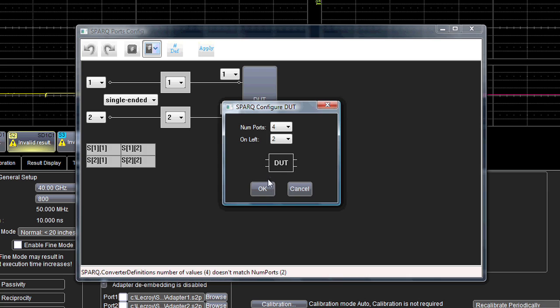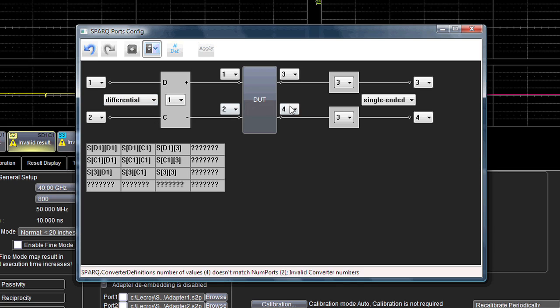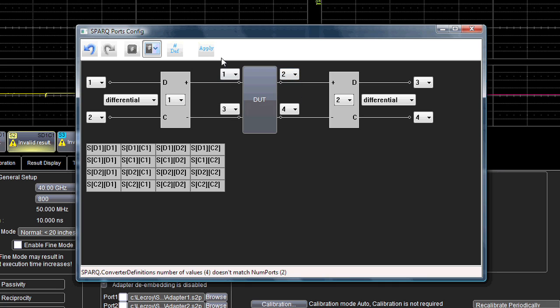Since we essentially have a two-port differential system, we'll set up the SPARQ to consider the system as such. The configuration screen you are seeing allows you to define the port mapping. In our case, ports 1 and 3 and 2 and 4 are the differential pairs.